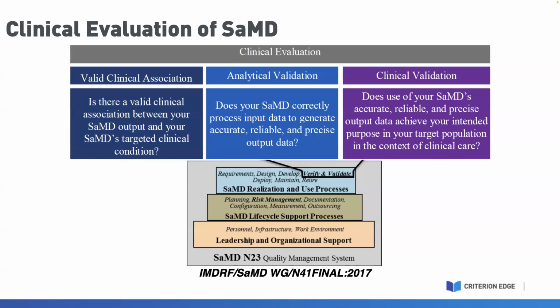So it's things like diagnosis, treatment, risk prediction, treatment response, or a positive impact on the individual or public health as a whole. So the clinical evaluation gets evaluated and determined during the development of the software as a pre-market and post-market approach. And it can be thought of more as the relationship between those validation experiments, validating your algorithm, and that clinical condition. So you really want to make that link between the scientific validity and the analytical validity, and then show the direct clinical impact.